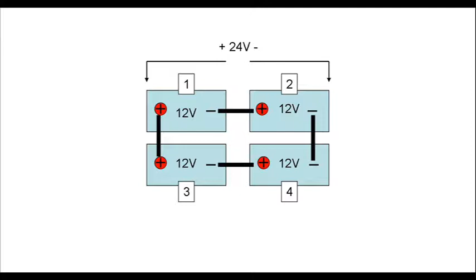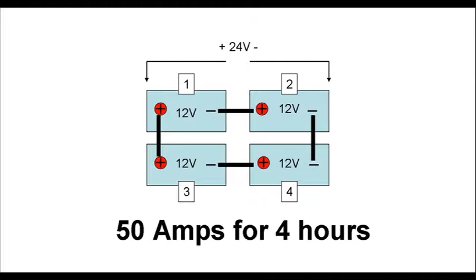Now the capacity of our battery bank is 200 amp hours because our 4 12-volt batteries are connected in the 24-volt configuration. 200 amp hours means that our battery bank can provide approximately 200 amps of steady DC current for 1 hour, or 100 amps for 2 hours, or 50 amps for 4 hours. So how long would it take our drill to completely drain our battery bank? Take the capacity of the battery bank, which is 200 amp hours, and divide it by the 8 amps that my drill uses. 200 divided by 8 equals about 25 hours.